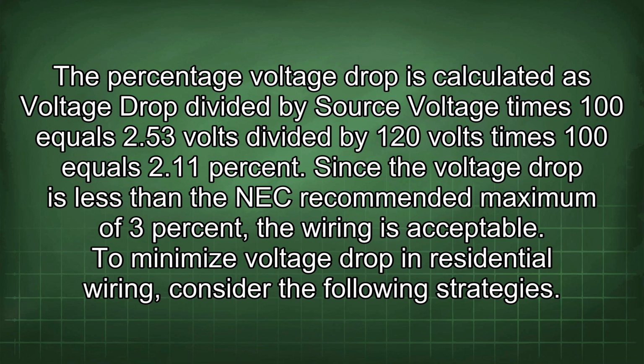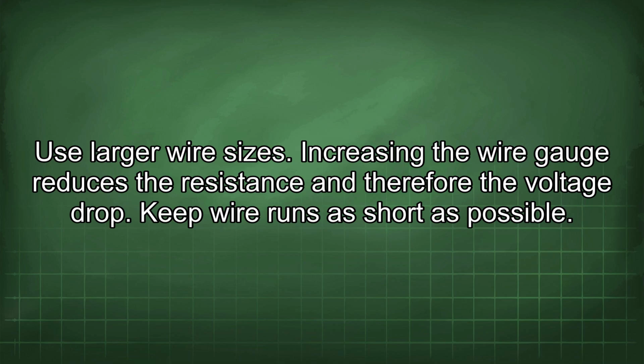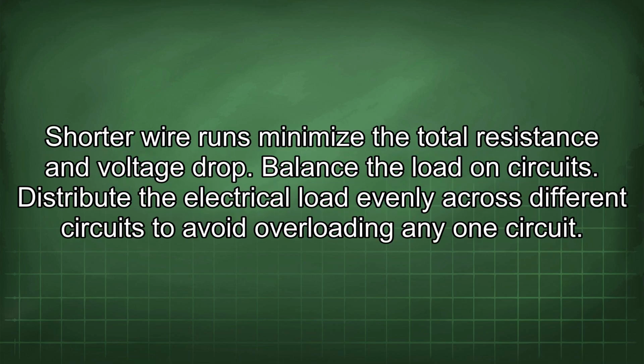To minimize voltage drop in residential wiring, consider the following strategies. Use larger wire sizes. Increasing the wire gauge reduces the resistance and therefore the voltage drop. Keep wire runs as short as possible. Shorter wire runs minimize the total resistance and voltage drop. Balance the load on circuits. Distribute the electrical load evenly across different circuits to avoid overloading any one circuit.